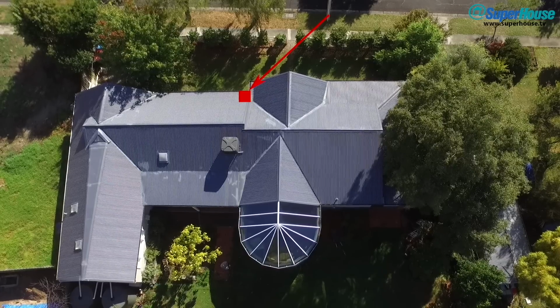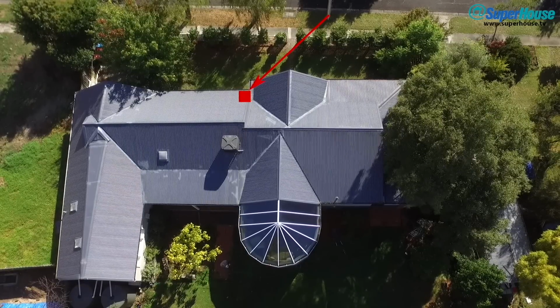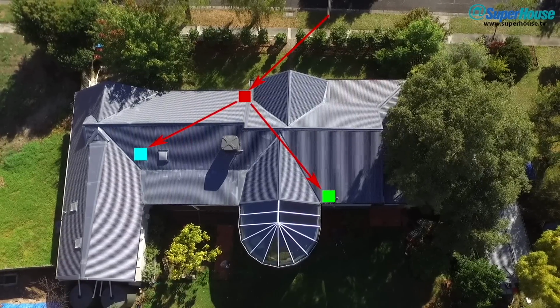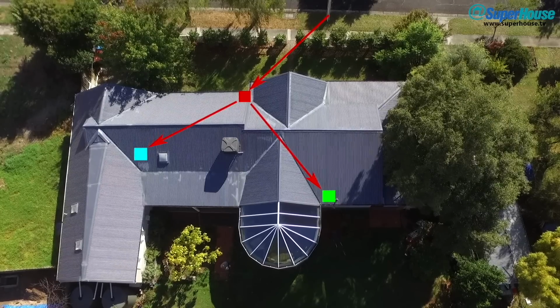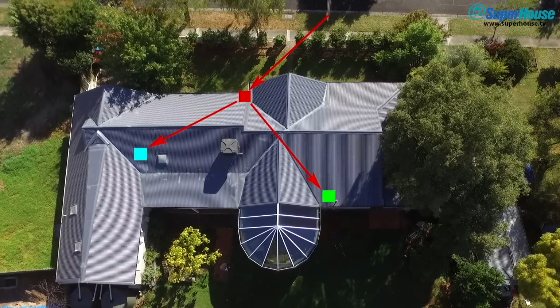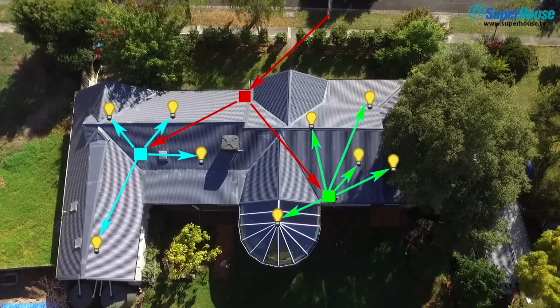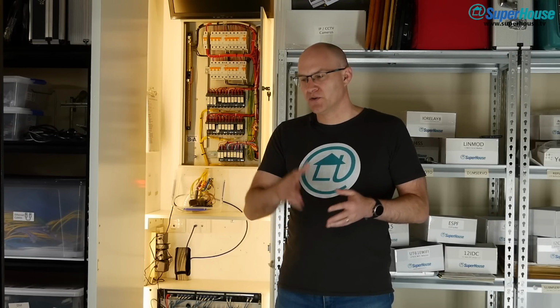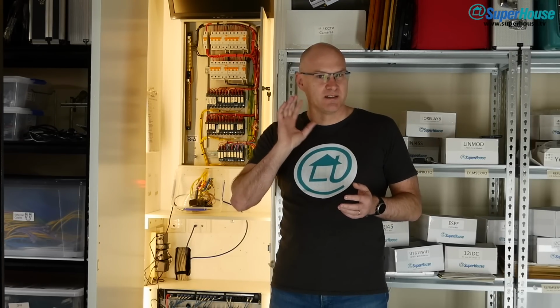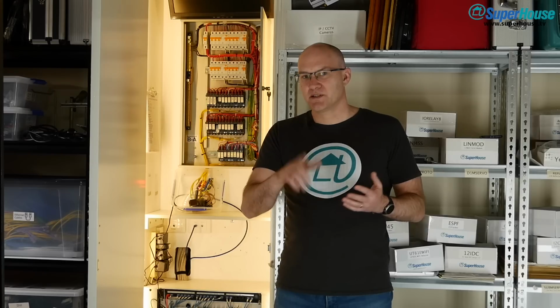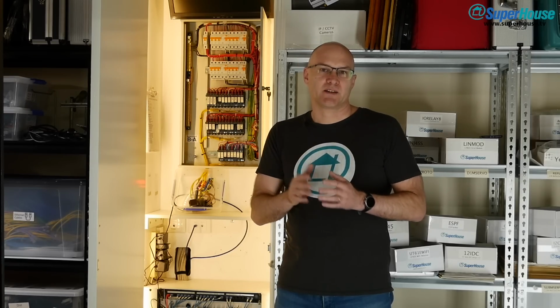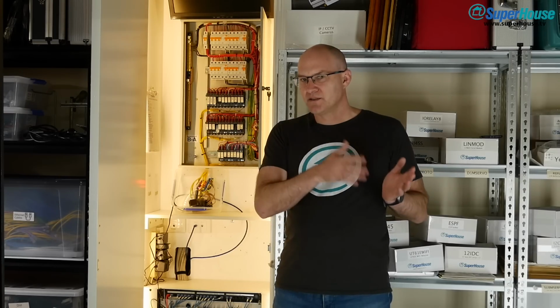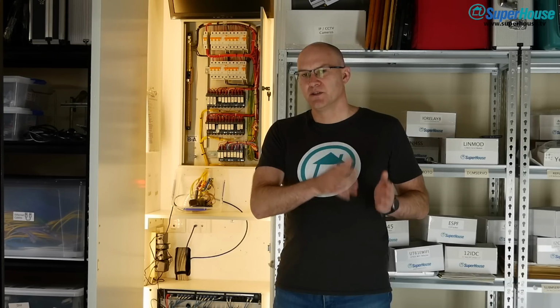Power comes in from the street to the main switchboard. From there, it's distributed to two sub-switchboards. Each of those switchboards contains relays, which are mounted on DIN rails, and they go out to control the loads. That way the control inputs, which could be from a smartphone or it could be from a control surface like a panel on the wall or a switch, aren't directly controlling the load. They are sending commands to the home automation system, which in turn turns the loads on and off.